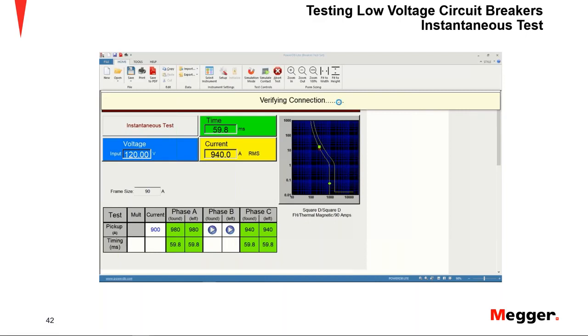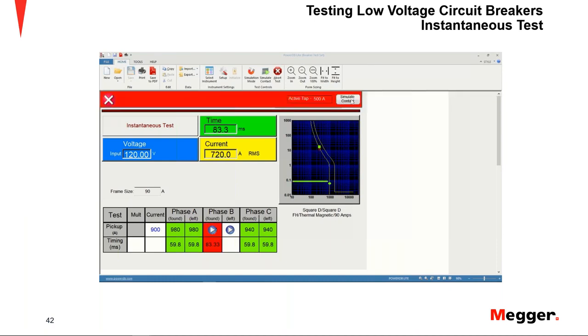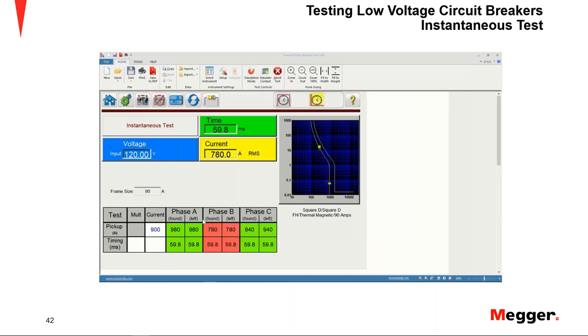So testing phase B now. And we're gonna make that B phase fail. I wanna show you how that looks in the report, right? A and C, good, they trip within the limits of the curve. B phase, it's a fail, right? It's a red result. So how does that look in the report?